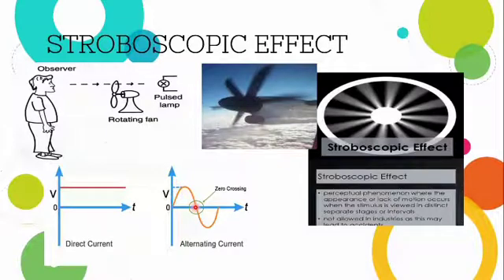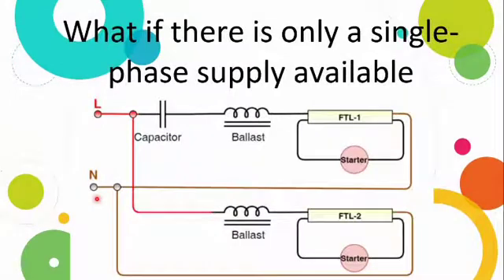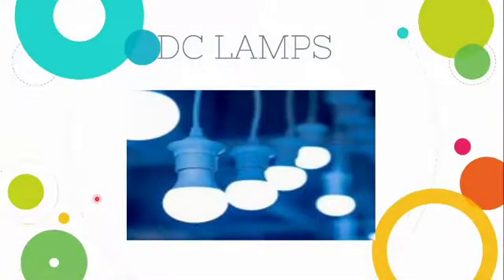To reduce the stroboscopic effect, there are three methods. First, if you use a three-lamp system, connect each lamp to a different phase — R, Y, or B — so they have different zero-crossing periods. Second, if you use a single-phase system, use twin tube lights with a capacitor in series; the capacitor creates a phase displacement between the two lamps, reducing the effect. Third, use DC lamps or LED lamps to eliminate the zero-crossing effect entirely.